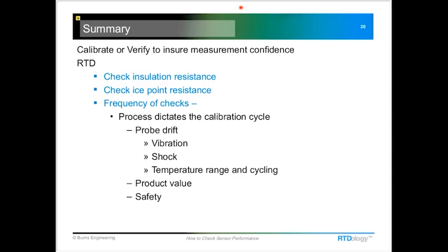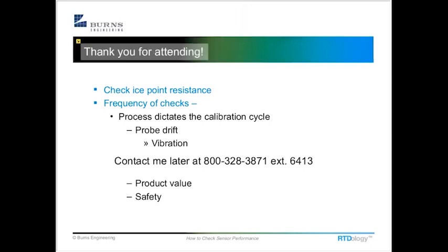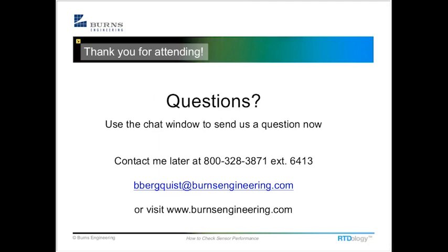So, I should mention too, I had a question a few days ago about a temperature probe in a freezer, running at some pretty cold temperature, and kind of difficult to get at and to check. They thought it probably hadn't even been checked for quite some time, which is a little bit concerning. But again, that's part of the process where you can't get at the temp sensor. That's going to help dictate maybe your calibration cycle, right or wrong. In that case, I think it probably should have been done more frequently than what had been done, but it was in a situation where it was pretty much a constant temperature, and it was on the cold side, so the temperature probes tend not to drift very much in those kinds of situations, and it may be that your frequency might be measured in years rather than months.